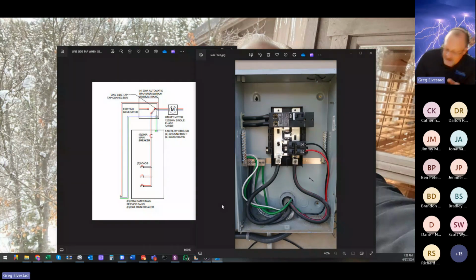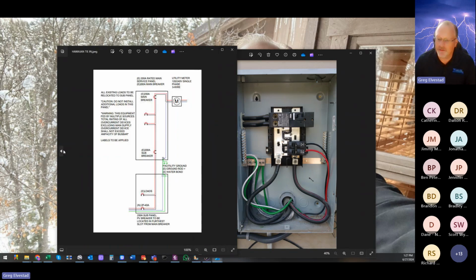Now, having said that, many of the manufacturers today have integration with standby generators. Enphase does this, Generac does this, Sol-Ark, and other companies out there that can do that. Not intentionally excluding anybody, just to highlight the fact that it does exist. They have done this. You must follow their explicit instructions on how to do that. If there's any questions at all, get with your technical support advisor from the manufacturer to talk about how to do that. It's possible to do that, but if it's just PV, please don't do that. Please don't try to connect with the same bus bar.